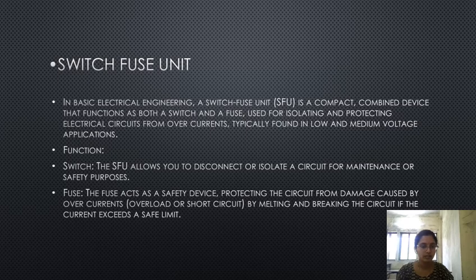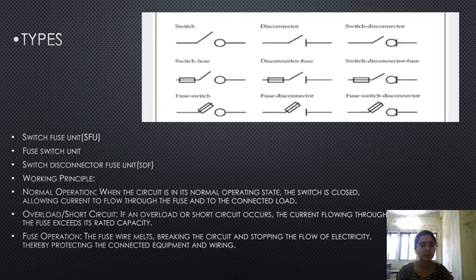Switch fuse unit. In basic electrical engineering, a switch fuse unit is a compact combined device that functions as both a switch and a fuse used for isolating and protecting electrical circuits from overcurrents, typically found in low and medium voltage applications. Its functions are: the SFU allows you to disconnect or isolate a circuit for maintenance or safety purpose. The fuse acts as a safety device protecting the circuit from damage caused by overcurrents by melting and breaking the circuit if the current exceeds a safe limit.